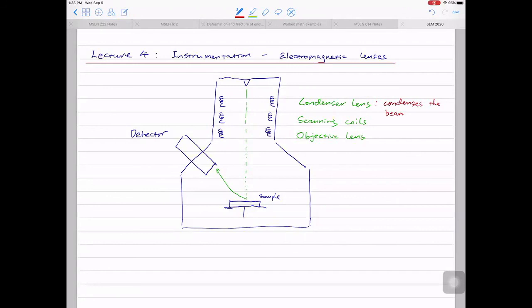Why do you want to condense the beam in the first place? Why converge the beam into a spot? In SEM, what we want to do is converge the beam to a spot to scan on the specimen, so we need a lens to condense the beam. Then after the condenser lens, we have the scanning coil — that's where SEM gets its other name. When we converge the beam into a spot or disk, we need to raster the beam across the specimen surface. So the scanning coil does the scanning.